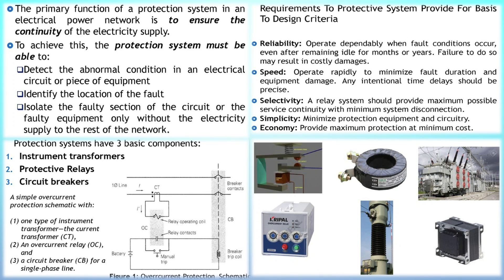The primary winding of a current transformer CT is connected in series with the line. The secondary winding of the CT is connected in series with the relay operating coil. The tripping circuit, which may be either an AC or DC source of supply, has the trip coil of the circuit breaker and relay stationary contacts connected in series.